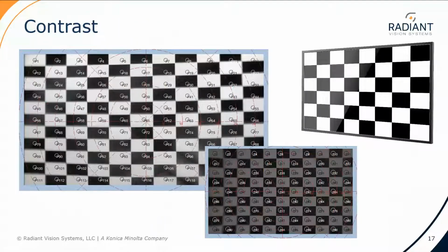So here are some examples. Contrast is measured as a ratio of the luminance between the dark and the light regions. Here we have an example of a checkerboard test image to perform this analysis. The concept is pretty straightforward. We measure the luminance of the white squares, and of course the dark squares, and we give a ratio between the two. We can also perform this test in different bright states of the display to help us truly understand the contrast ratio limits of the technology we're inspecting.